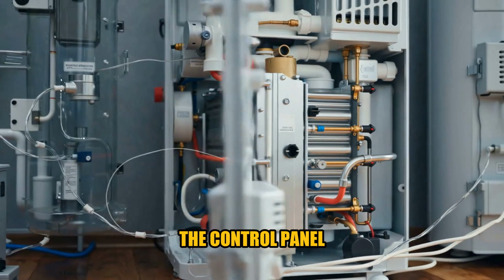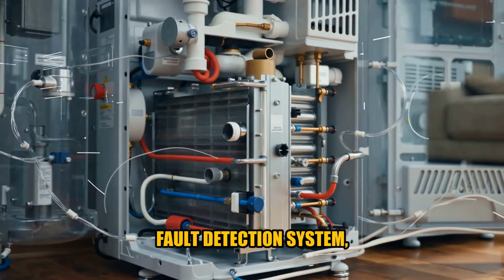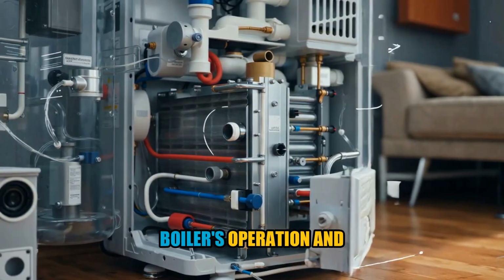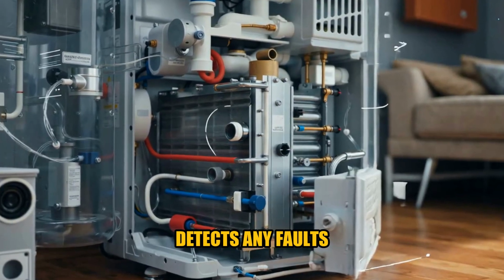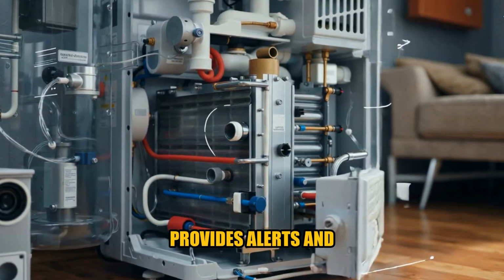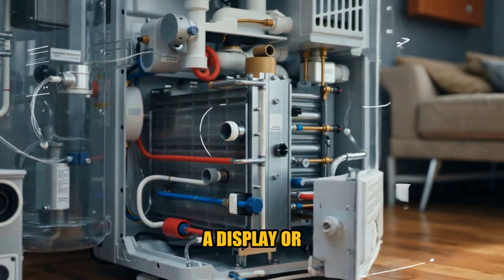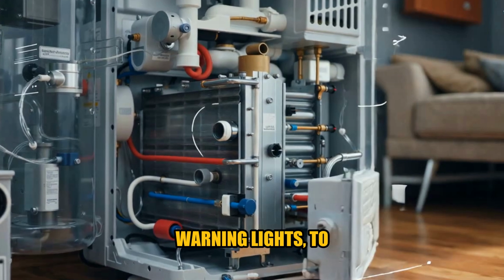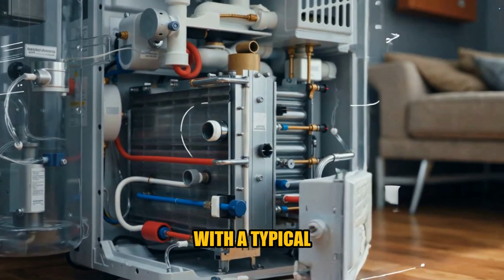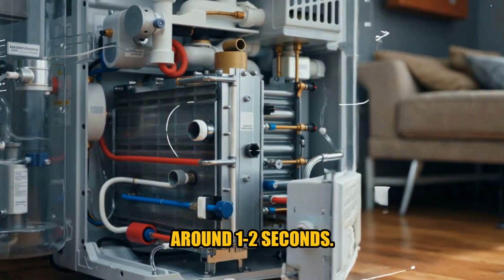The control panel also includes a fault detection system, which monitors the boiler's operation and detects any faults or anomalies. It provides alerts and notifications, typically through a display or warning lights, to indicate any issues, with a typical response time of around 1 to 2 seconds.